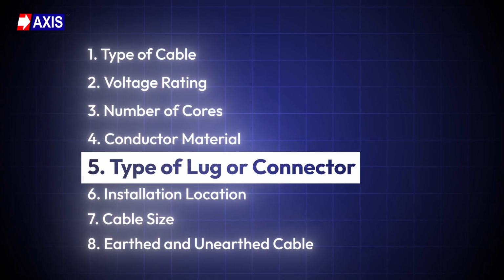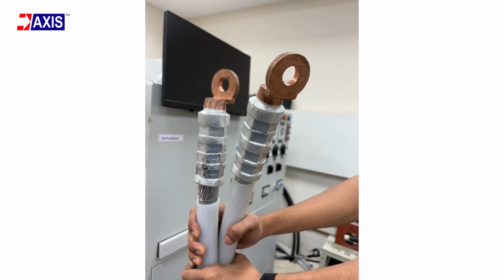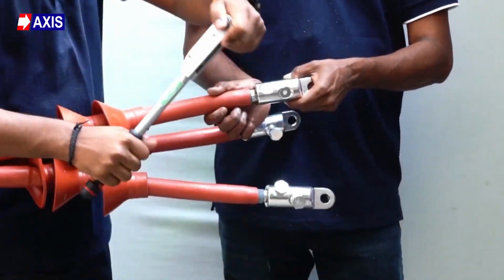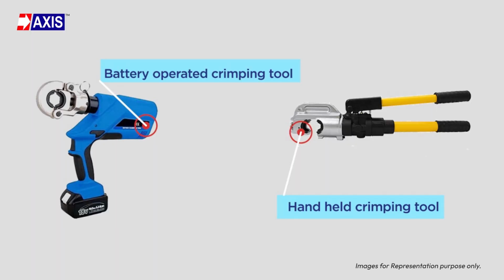Number 5, the type of lug or connector. Termination and jointing kits use either crimped or shear head lugs and connectors. Crimped lugs require a crimping tool and the correct die. Shear head lugs do not require crimping tools. You tighten them until the head breaks at a fixed torque, which ensures proper tightening. So, you must choose the lug and connector type based on your requirement.